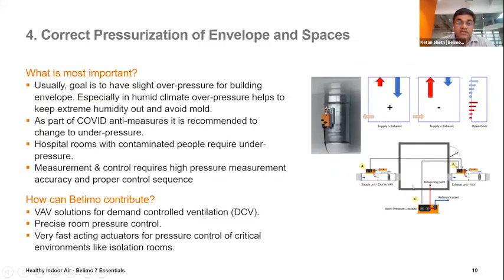The fourth one is the correct pressurization of the envelope or the spaces. Generally, the designs are always that the building is a little bit on the over pressure compared to the outside, so that the outside high humidity can be avoided and the mold can be avoided. During the COVID-19 measurement, this has been changed, and based on the application, whether it's over pressure or under pressure has been designed. One example is the hospital rooms where the contaminated people are kept. They are always kept under pressure so that the virus will not spread to the rest of the areas.